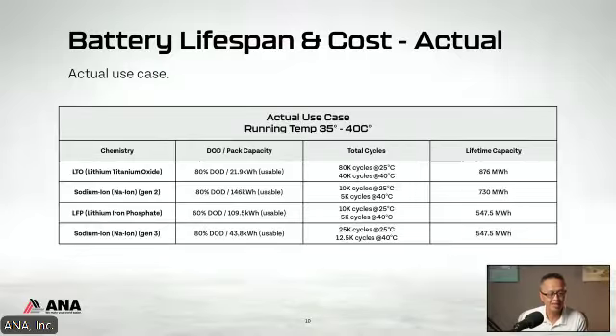That is the cycle life at 25 degrees. Now we know that in actual applications, it's very difficult to maintain that temperature. So let's assume that everything's at 40 degrees. In an actual use case, let's assume these batteries are at 40 degrees, so let's cut those numbers in half. That's 40,000 for LTO, 5,000 for sodium and LFP, and 12,500 for sodium third gen. If that's the case, then the lifecycle capacity is what's displayed there: 876, 730, and about 547 for both LFP and third gen sodium.